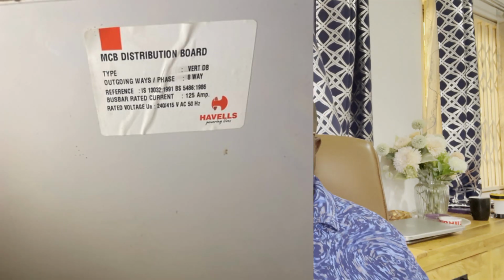Okay. Another issue was, I guess one main issue here, that this electrician that I met was the 4th electrician on this building. They've been changing electricians over the years for whatever reason, so it's not entirely his fault, to be fair to him. Now, the distribution board that was installed for this house was too small, far too small. They installed an 8-way 3-phase distribution board, and all the breakers are completely full up, to the extent that they had to come off the supply cable to put a branch connector to connect 5 AC units. So 5 AC units are not going via the distribution board.